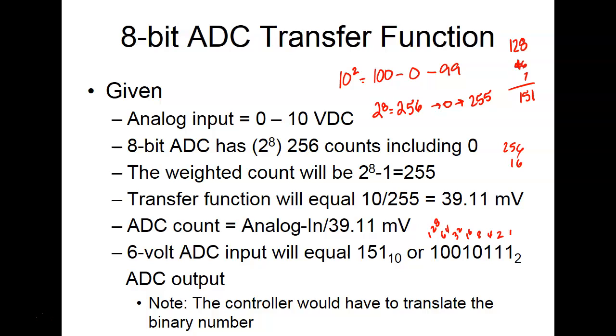So right now I'm saying 151 equals 60 degrees. All we have to do with our program is multiply 151 by that transfer function, and it would give us the degrees. So what do you say? We take 60 divided by 151? Yeah, 0.397, and then we.